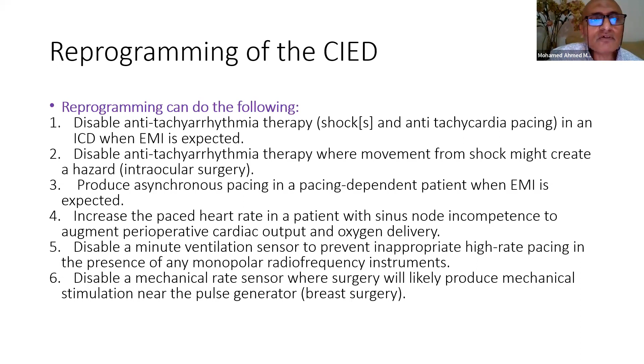What is the difference between reprogramming through a machine or a magnet? For the reprogramming machine, we have to call the CIED team, the cardiologist who is dealing with the cardiac devices, and he will bring the machine and reprogram the device through it. But with a magnet, if it is available, we just need to put this magnet directly on the device. Reprogramming using the magnet will stop the defibrillation function of the ICD. And if this ICD has a pacemaker function, it will do nothing with the pacing.